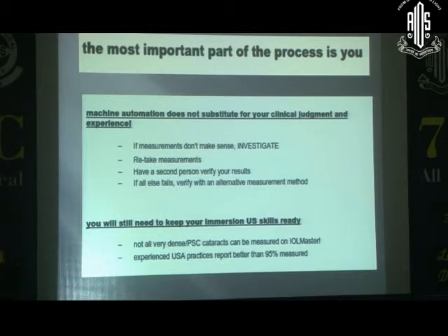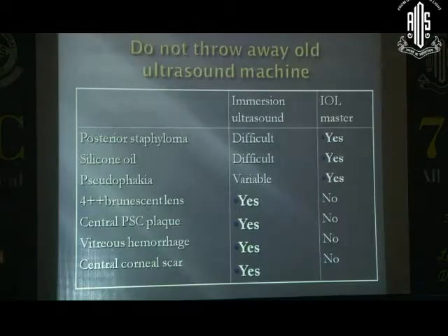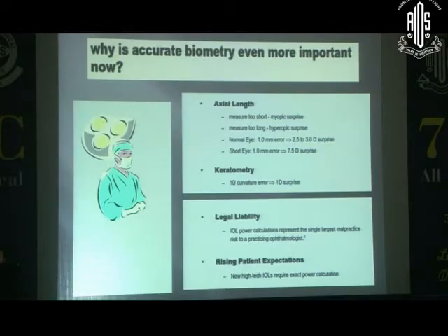You will need to keep your immersion ultrasound skills always ready, even in the era of IOL Master. The reason being there are certain situations where IOL Master doesn't work, and this is where immersion ultrasound is useful: a 4+ Brunescent cataract, a central posterior capsular plaque, a vitreous hemorrhage, or a central corneal scar. So immersion should not be thrown away just by getting a very good feel or look at the IOL Master. Why is it so important to measure accurately? Obviously, there are legal liabilities, but more often than not, it is your expectation and the patient's expectation which you need to fulfill after the surgery.